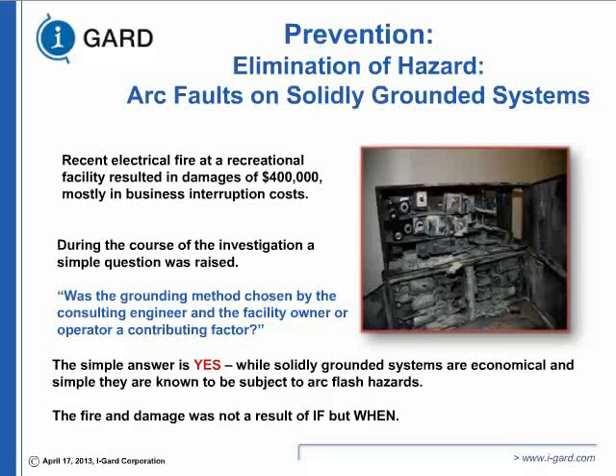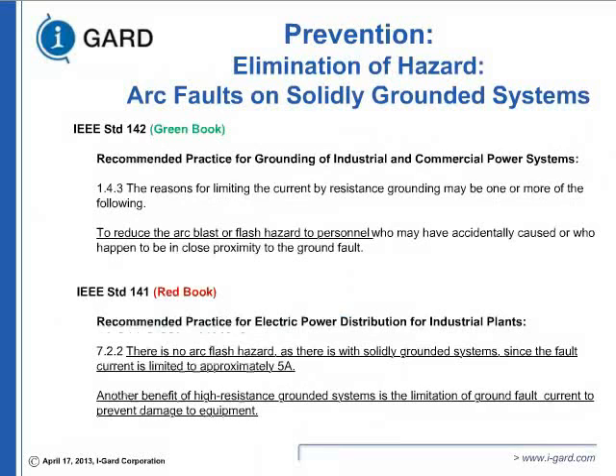Industry has experience. In the industry I work with, we had experience where a motor terminal box cover blew apart. Some of you may have seen transformer throat covers coming apart. That was primarily due to a solid grounded system creating so much energy during the first fault. Arcing fault on a solid grounded system.